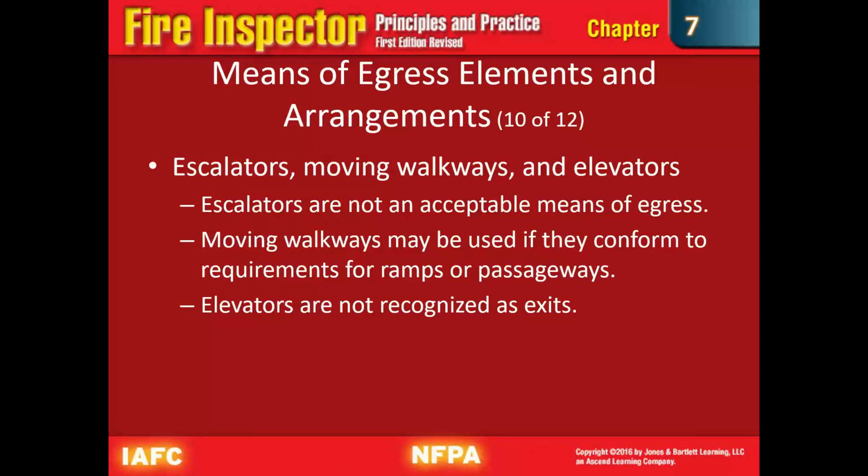Well, when they went back and had the fire alarm systems installed, a fire alarm would typically cause an elevator to go down to the bottom floor and pretty much be locked there for firefighters to use to get to the fire floor. Well, if there was a fire and there was a handicapped person, in whatever means or condition, they would pretty much be stuck up there if the elevator went down to the first floor.